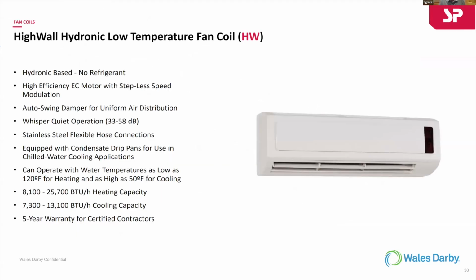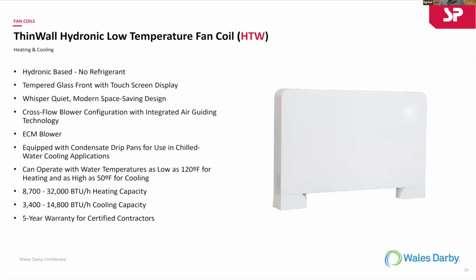So this would be a wall unit, similar to your mini split type setup, except we're running hot and cold water to it. We're running PEX tubing, which is fairly easy to run. And again, we're not really worried about things like refrigerant leaks in walls, or at least not as much with these type of units. Okay. And then you have your wall emitter, same thing, got the little fan in it, can be used for heating and cooling. These are kind of units you might use on a brand new gut job where the whole house is being redone, the whole building's being redone.